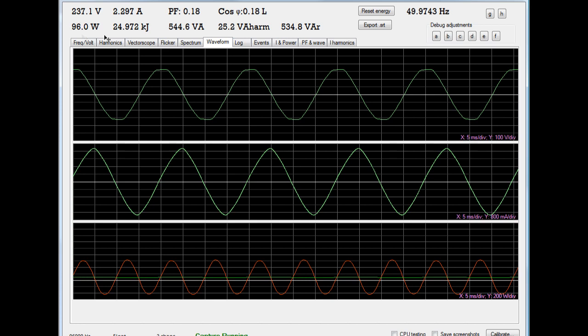So how can that be? How can the watts be one half while the amps are three times as much? Well, this is how. Look at the power curve, and what do you notice about this? Well, the fact is the power curve is going down below zero. We're getting a negative watt reading here. Negative about 450 watts here. So what does that mean?